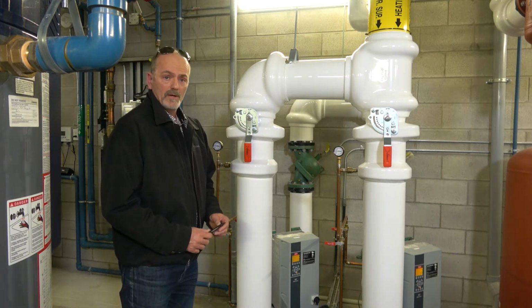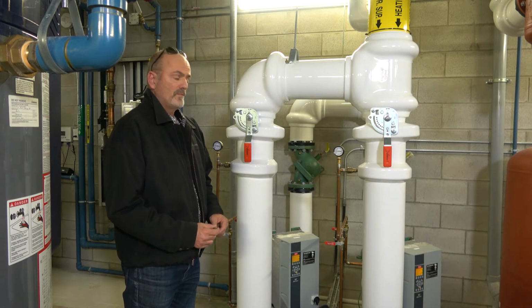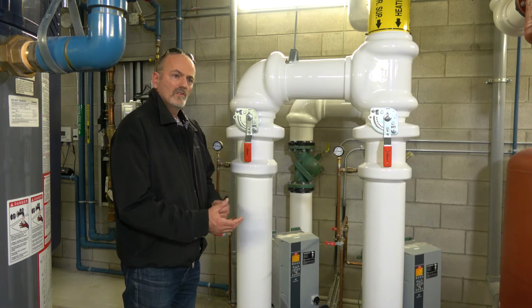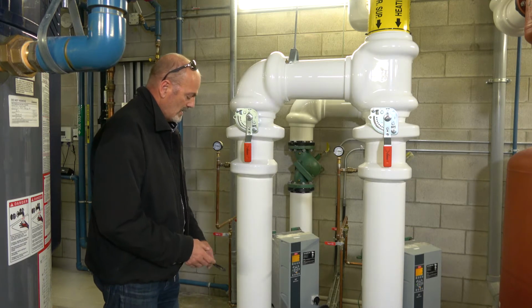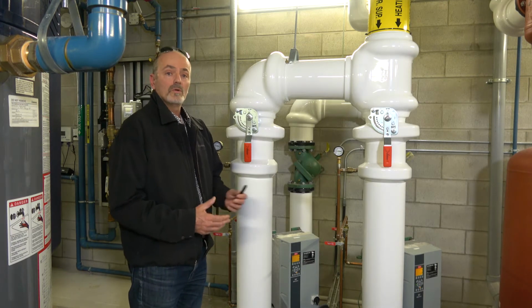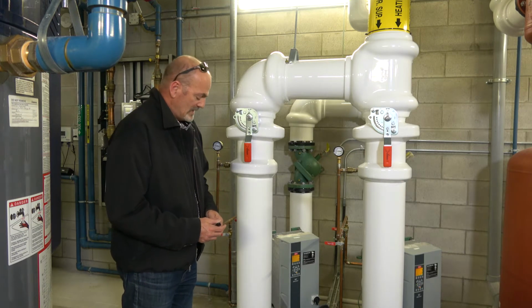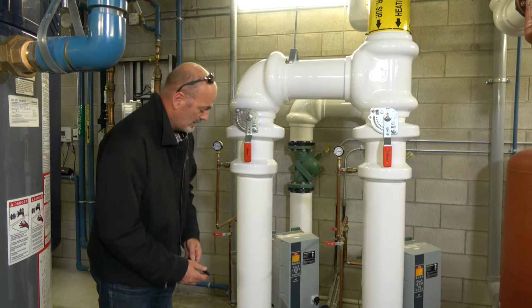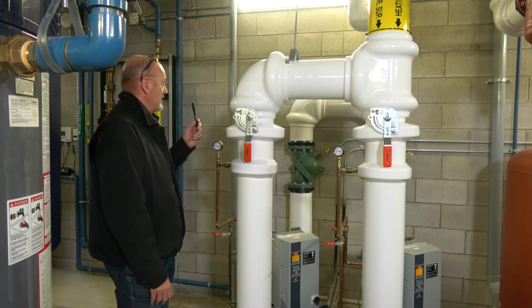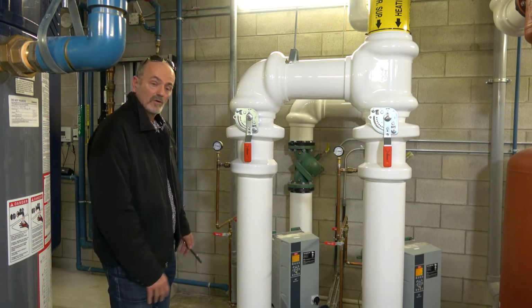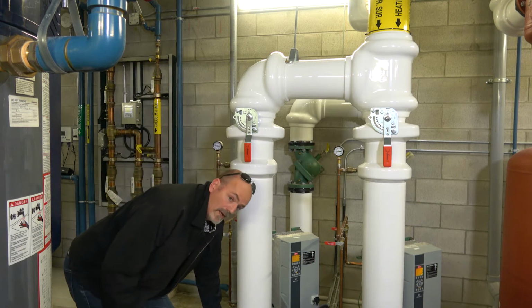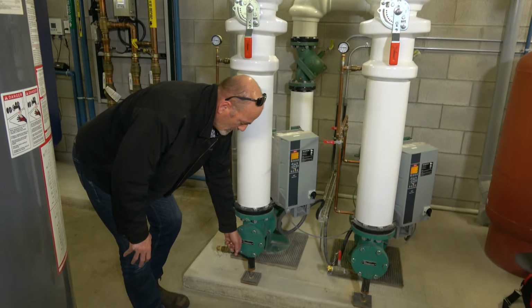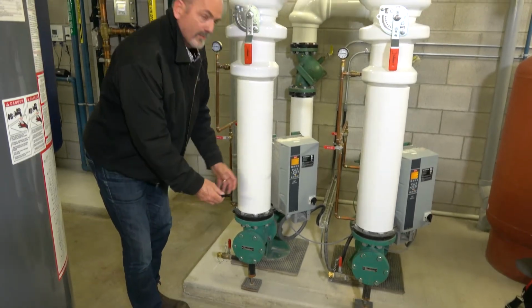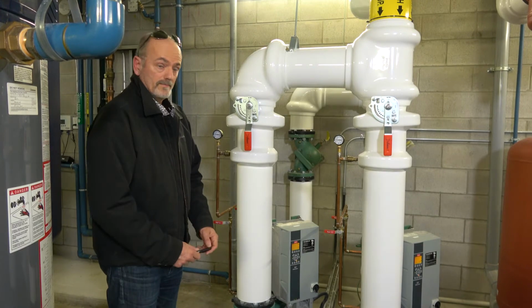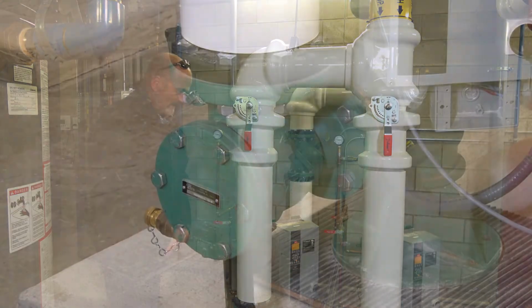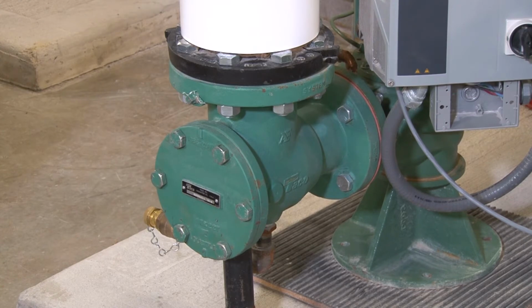It also has a strainer in it, a system strainer. If pump performance is changing or you're getting some noise out of the pump, it's cavitating, it could be that the strainer has gotten loaded up with debris and needs to be removed and cleaned and then put back in. You can remove it again by isolating in and out, allowing the system to cool, draining the valve. There is a drain right here. And taking these radial bolts off, removing the plate, backing out the strainer, flushing it, putting it back together, just like you took it apart, okay? And in this case, it's a rubber gasket, so it's reusable.